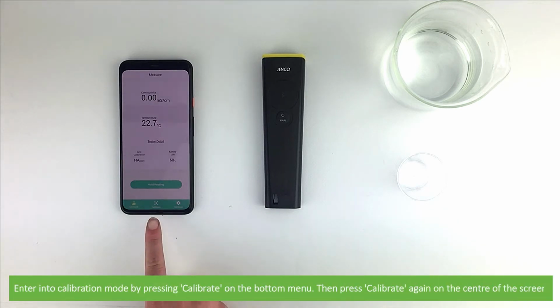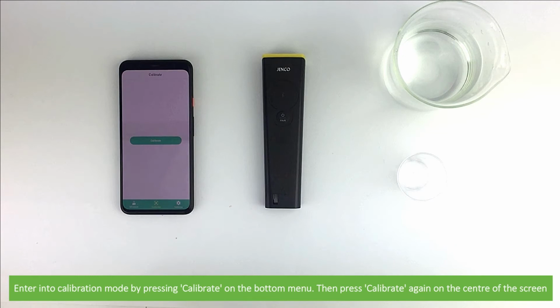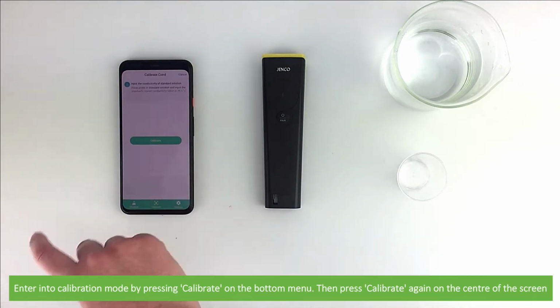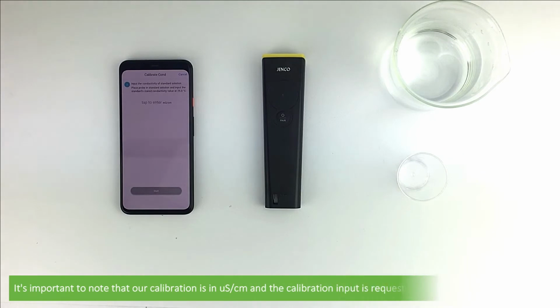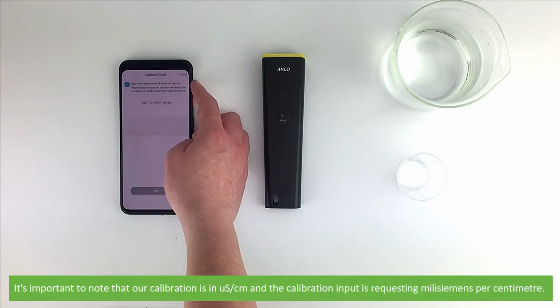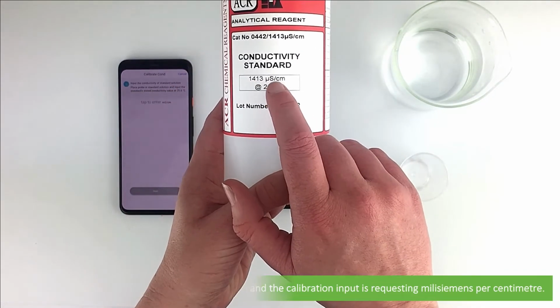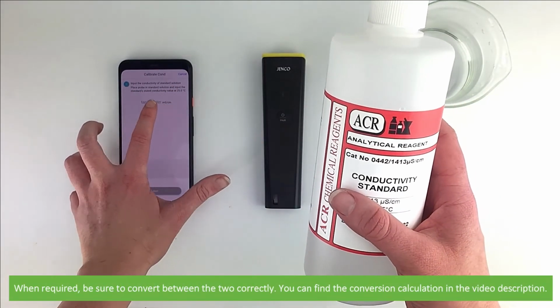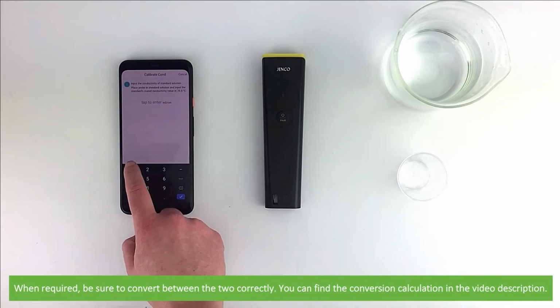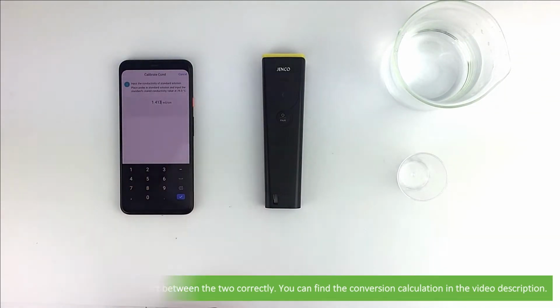To start, enter into calibration mode by pressing Calibrate on the bottom menu, then press Calibrate again on the centre of the screen. It's important to note that our calibration solution is in microsiemens per centimetre and the calibration input is requesting millisiemens per centimetre. So when required, be sure to convert between the two correctly. You can find the conversion calculation in the video description.